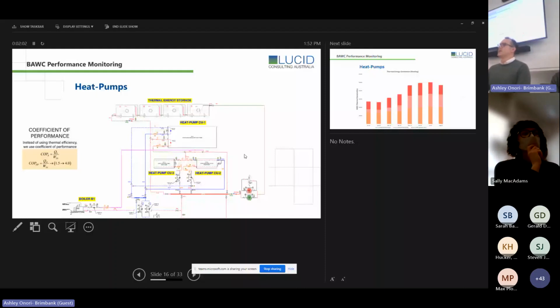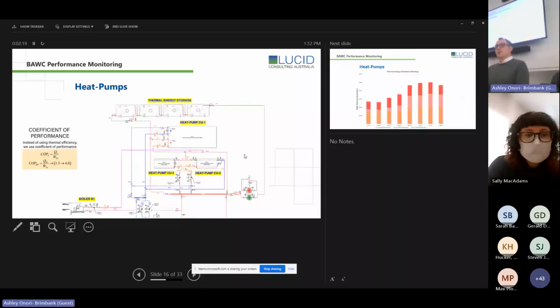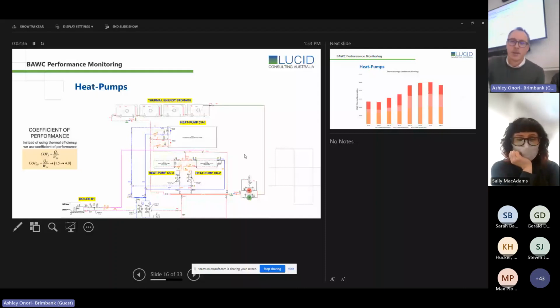So it's 53 degrees out to the field, out to devices within the building, so heating coils and heat exchangers, etc. And what's coming back from the field is 48 degrees. So there's a 5 degree temperature differential between the flow and return out to the field and back to the heat pumps. That's a really important aspect because you're trying to optimize efficiency of the heat pump units. If you tried to operate these heat pump units up to 80 degrees in terms of the thermal generation, you'd see that there would be a drop-off in efficiency. So that's another key takeaway for this.